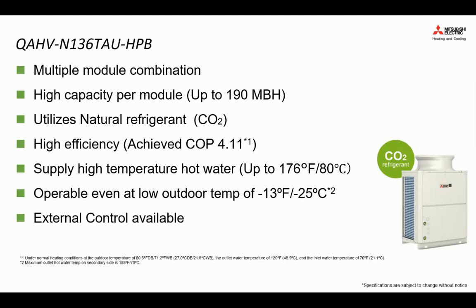So just to recap, the unit has multiple module combinations. It has high capacity per module. While the nominal capacity is 136 MBH, it can actually go up to 190 MBH, depending on the condition of the site and depending on how you design it. It utilizes natural refrigerants such as CO2, so very low global warming potential, which is 1.